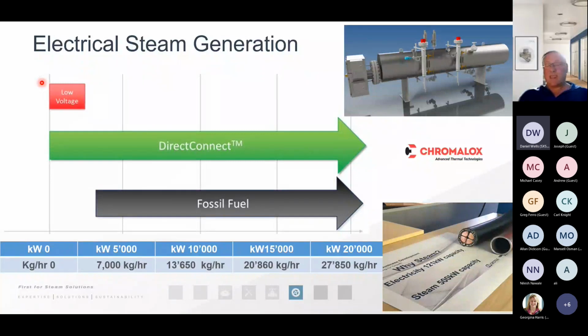In other words, we can use the existing steam boiler, remove the burner, and put an electrical element on it. Again, we're retaining the existing water treatment regime, the existing steam boiler, and the existing infrastructure. It means that we can produce steam in exactly the same way that we were doing before, but we've moved towards that net zero.